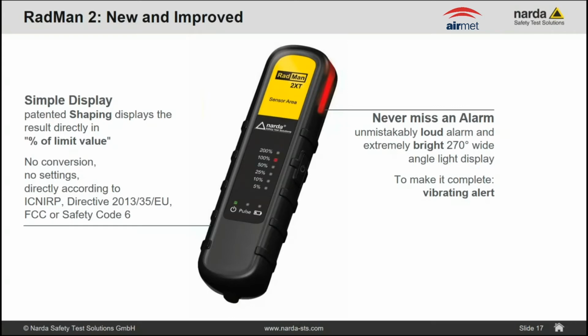So you have these 3 alarms if the limit is being exceeded, and then by the law or by the standards, you still have 6 minutes to get out of the radiation hazard zone if it indicates 100%, because that is based on a 6 minute integration time, where you have the maximum absorption of energy and the maximum heating effect.